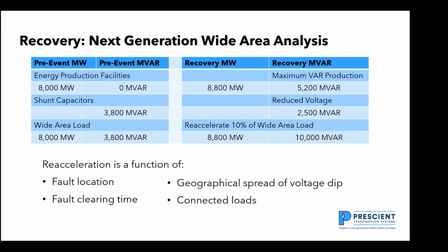I'm looking at this, and how do I tie it all together? Well, I'm going to look at pre-event conditions, and I'm going to look at recovery conditions. And this is a wide area blackout. So wide area blackout means we're talking about very high amounts of load. So we're looking at maybe 8,000 megawatts of load in this analysis, and the power production facilities aren't producing any MVAR. All the MVAR that I need for the system is coming from shunt capacitors. So I've got 3,800 MVAR of load, which I'm supplying from capacitors, 8,000 megawatts of energy that I'm supplying from generation facilities.